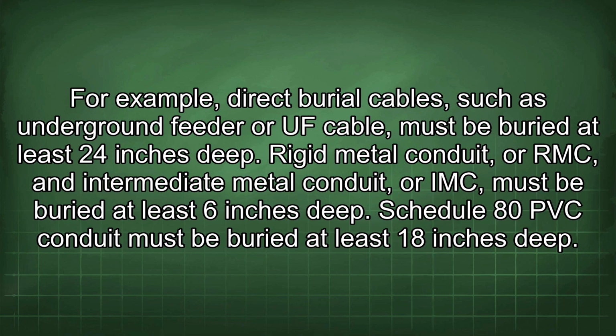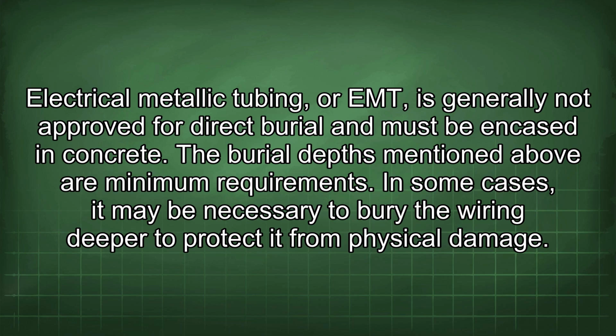Rigid metal conduit, or RMC, and intermediate metal conduit, or IMC, must be buried at least 6 inches deep. Schedule 80 PVC conduit must be buried at least 18 inches deep. Electrical metallic tubing, or EMT, is generally not approved for direct burial and must be encased in concrete. The burial depths mentioned above are minimum requirements. In some cases, it may be necessary to bury the wiring deeper to protect it from physical damage.